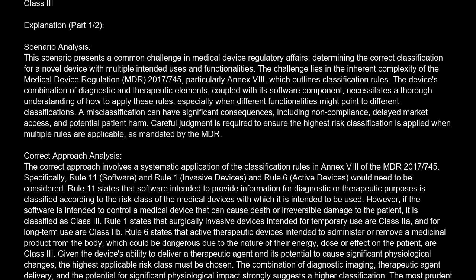A misclassification can have significant consequences, including non-compliance, delayed market access, and potential patient harm. Careful judgment is required to ensure the highest risk classification is applied when multiple rules are applicable, as mandated by the MDR. Correct approach analysis. The correct approach involves a systematic application of the classification rules in Annex VIII of the MDR 2017/745. Specifically, Rule 11, Software, and Rule 1, Invasive Devices, and Rule 6, Active Devices, would need to be considered.